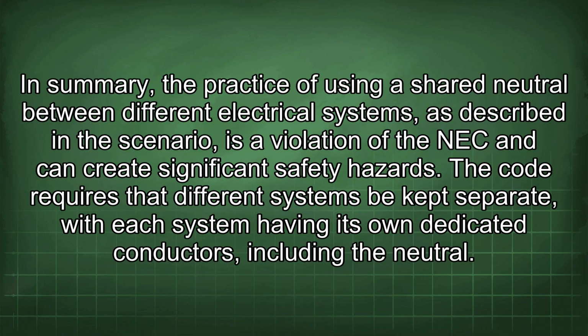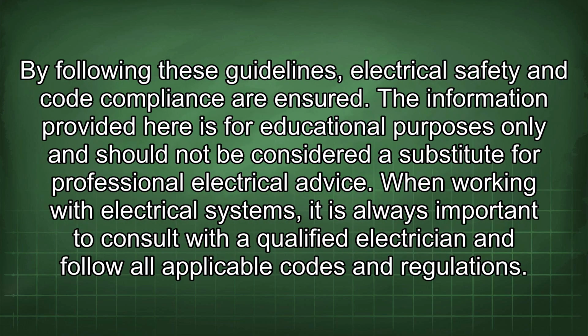In summary, the practice of using a shared neutral between different electrical systems, as described in the scenario, is a violation of the NEC and can create significant safety hazards. The code requires that different systems be kept separate, with each system having its own dedicated conductors, including the neutral. By following these guidelines, electrical safety and code compliance are ensured.